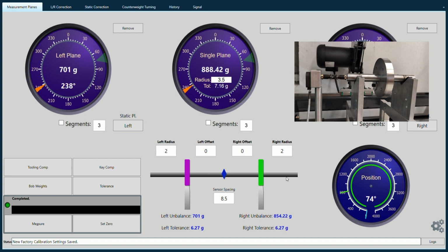Start by rotating the arbor so that the weights are positioned directly at the 12 o'clock position. Once they are here, press Set 0 in the lower left-hand corner of the interface. This step informs the machine that the 0 position is where the weights are, which is crucial for accurate calibration.